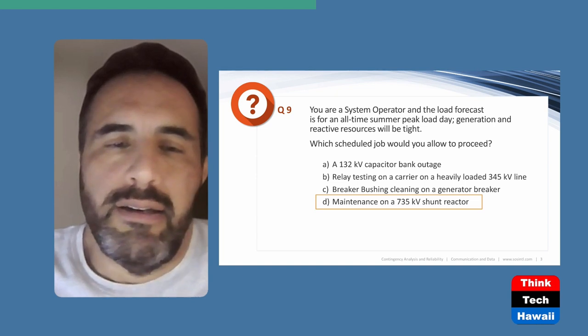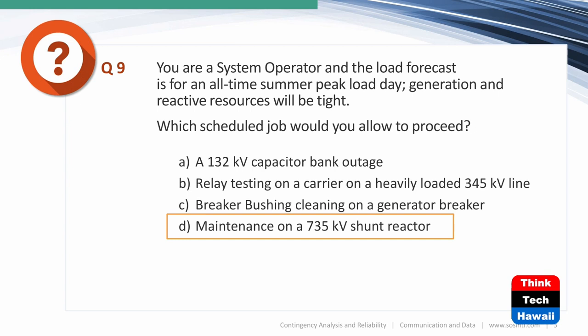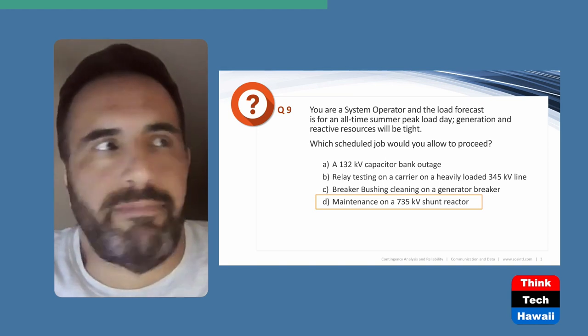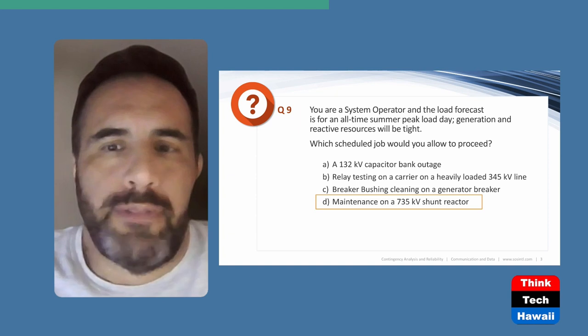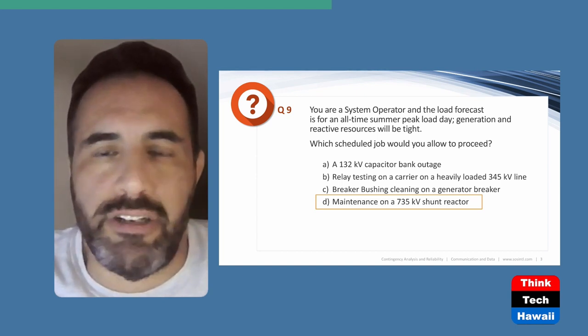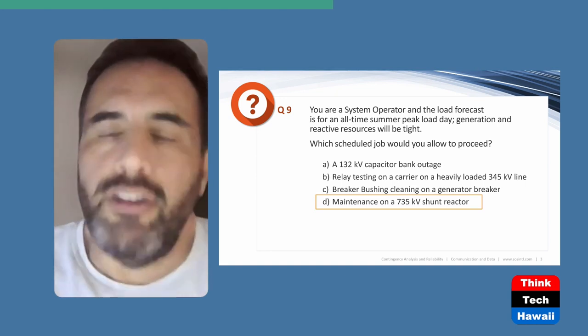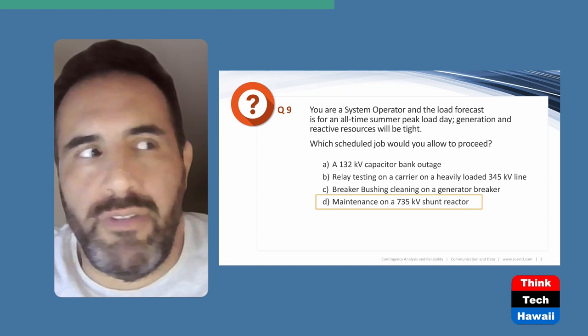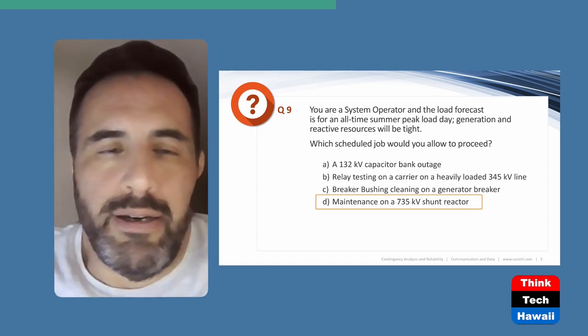Breaker bushing cleaning on a generator breaker — they usually clean breakers with distilled water at high pressure — always carries the risk of contamination, a flashover, and tripping a generator. You could lose a lot of generation in that incident. That's not a good thing when you're already maxed out with generating resources online and serving peak load. C is also not a good answer.